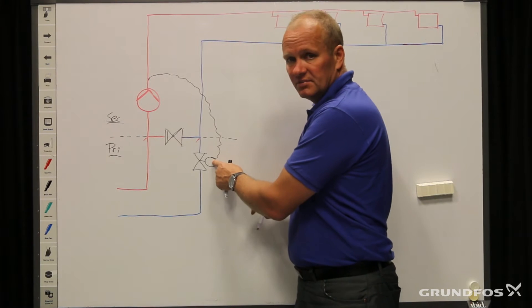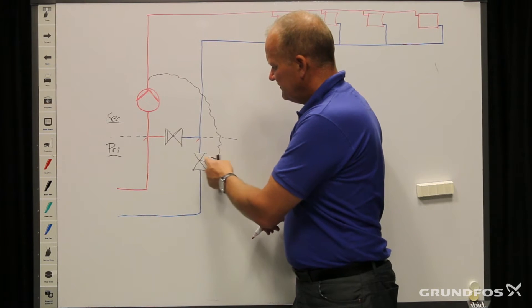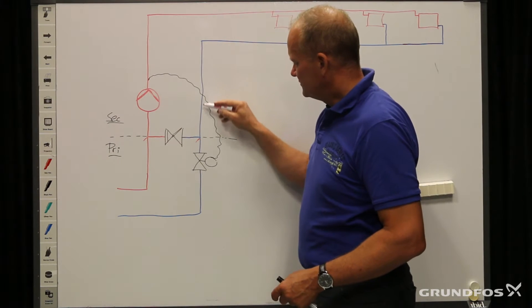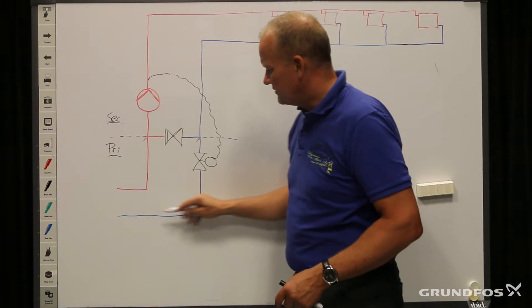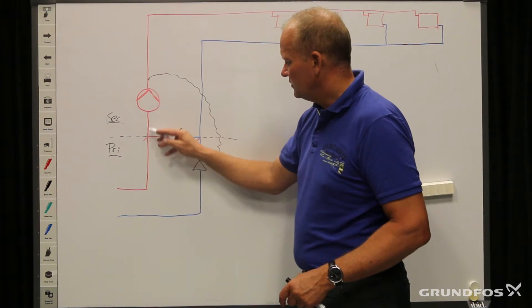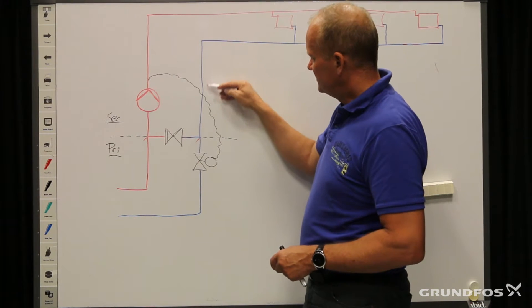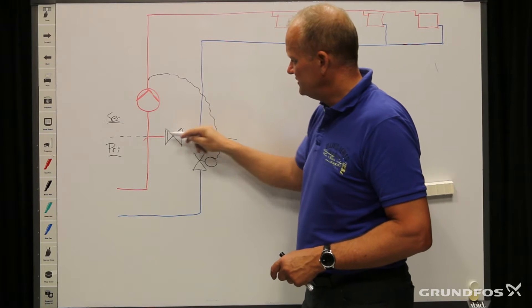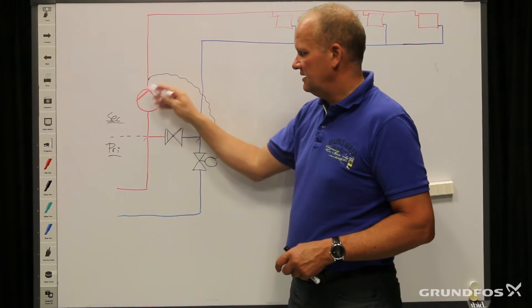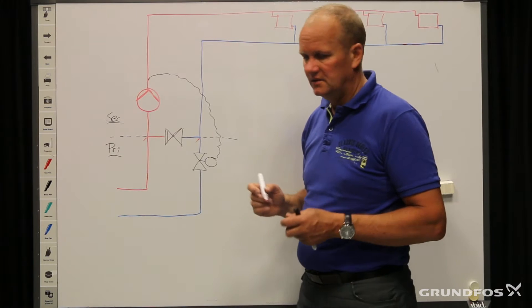The motorized valve is placed on the primary side. When this valve is opening and closing — if it's opening, it allows the return water from the system to go directly back to the main source, and then fresh hot water can be let into the system. But if it's closed, then the water coming back from the system is recirculated all the time out in the system, thereby adjusting the flow temperature to the level which is currently needed.